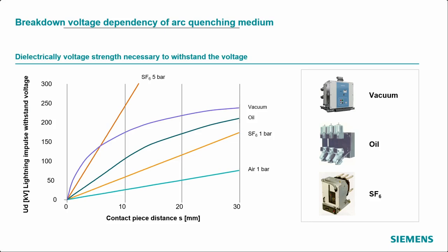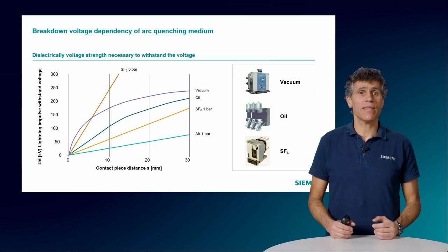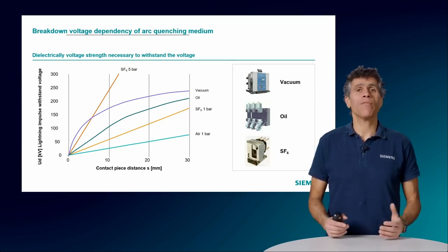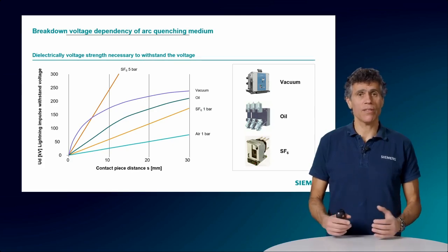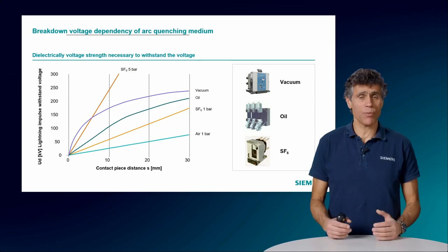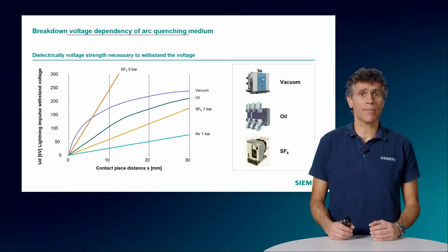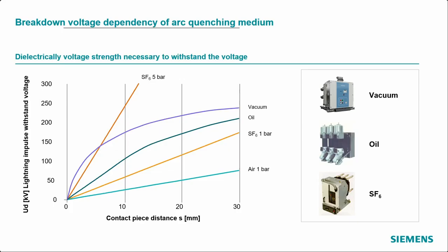This happens sometimes accidentally when someone inserts a metallic object and connects both sides of the plug, or when a faulty cable, short-circuited, is used. The distance between the poles is not enough to withstand the electrical stress. What about the medium? Though vacuum is commonly used, alternatives include pressurized and non-pressurized SF6, sulfur hexafluoride, and oil.